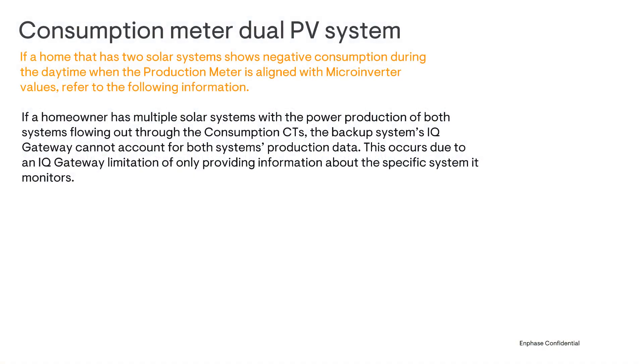Before troubleshooting, make sure that both PV systems have metering capability. Next, you'll need to verify whether the system's production is being measured through the consumption CTs of one or both IQ gateways. A single IQ gateway cannot account for both systems' production data, since it only reports data from the specific system it monitors.